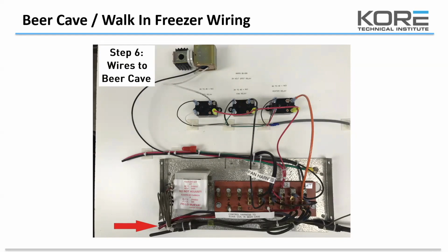This particular picture is showing the additional harness for the beer cave. In the beer cave, we usually have 2 coils. So we'll take 3 wires from what we call the master coil. The black wire is actually going to H1. That will supply all the power to the fan and the heaters in the slave coil.